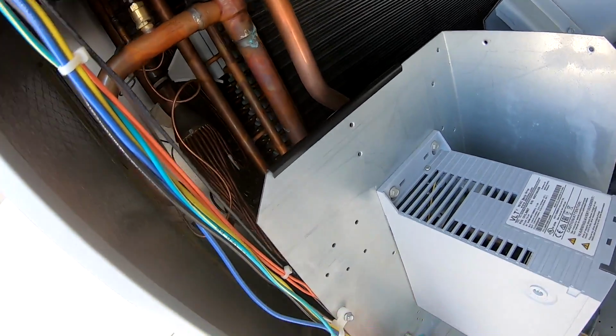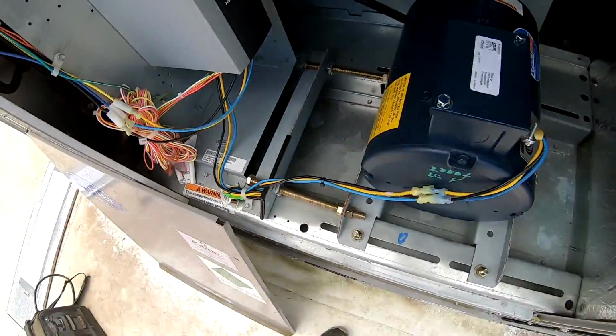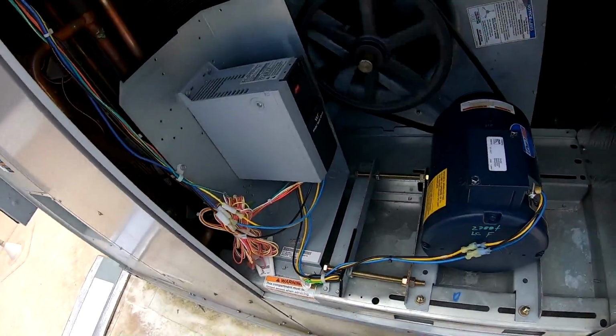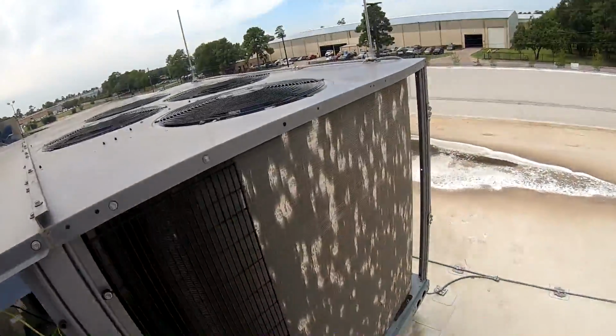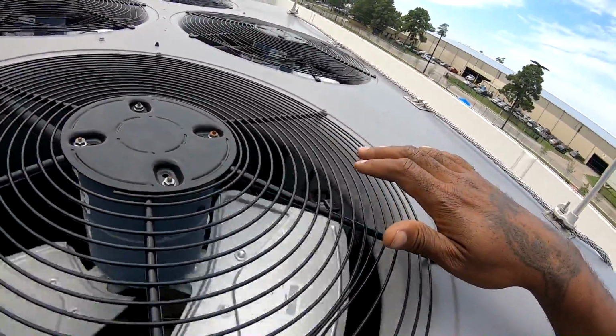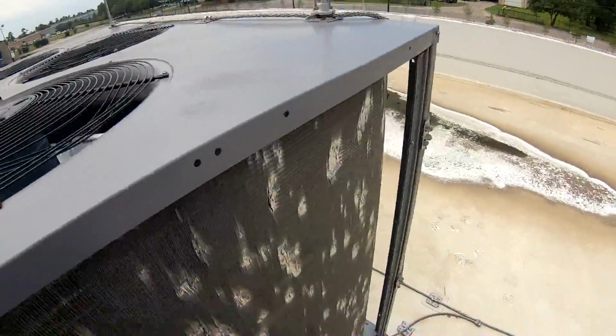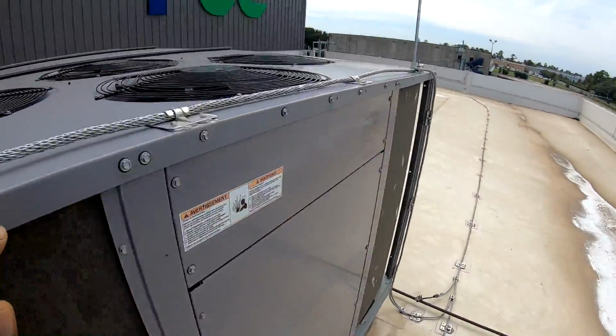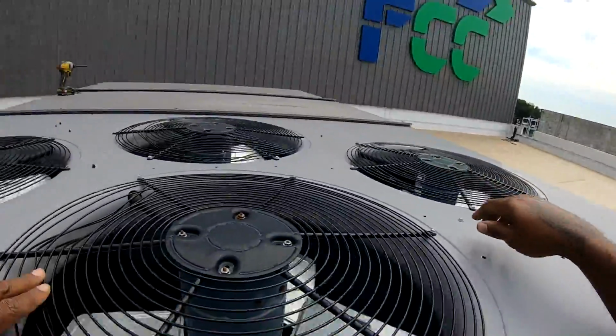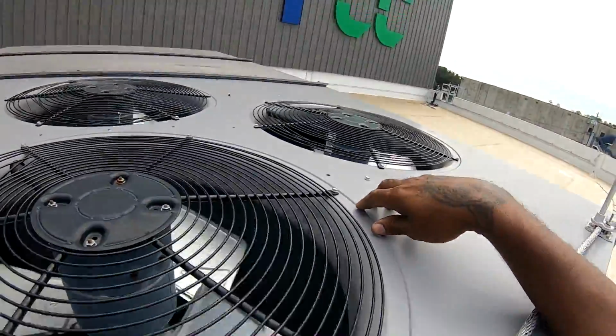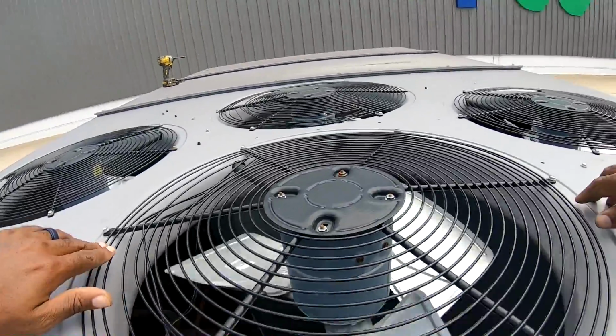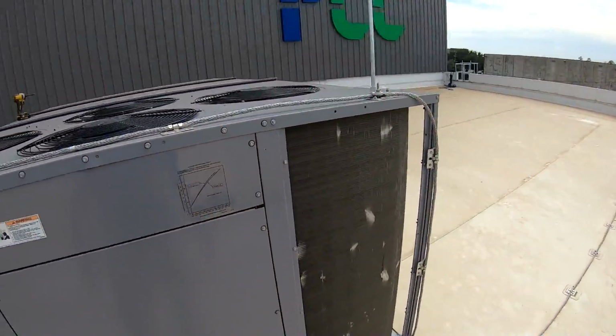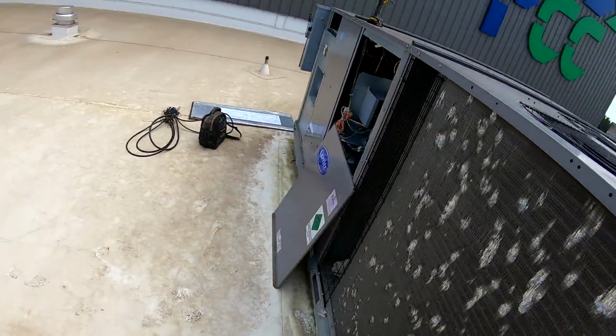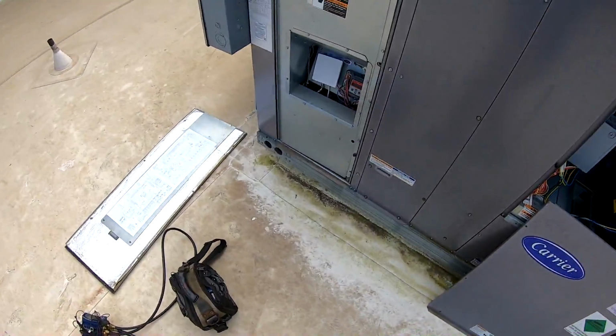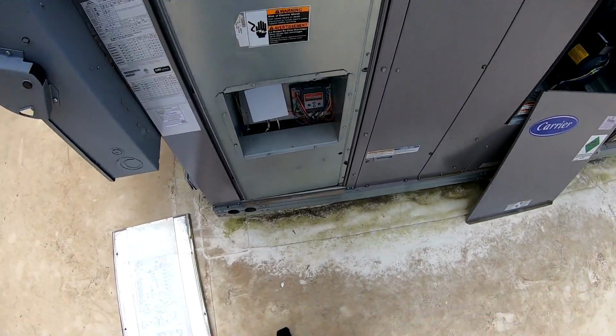There's a little condensation. I put my gauge on, but it's just short cycling. I bet it's going off on high head pressure. See, none of them fans work. And it's warm enough out here, I know it needs more fans than that. All right, so I'm figuring out how to get this door off. Let's see.